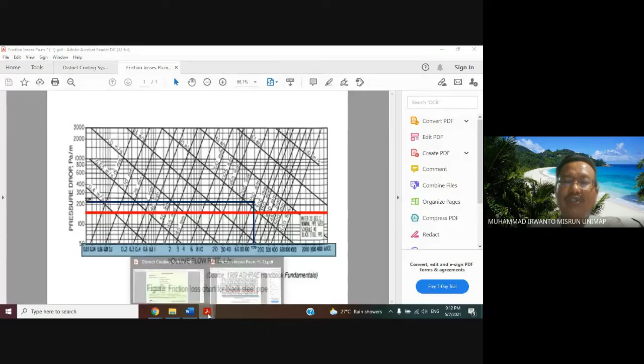Q from here we obtain, Q is 139 liter per second and the diameter is 250 millimeter, or 0.25 meter. So the horizontal axis is flow rate. Please look at the value of flow rate in liter per second. For the 100 and 200, one vertical line here is 120 liter per second. So for 139 liter per second, it is around this one, the blue color.